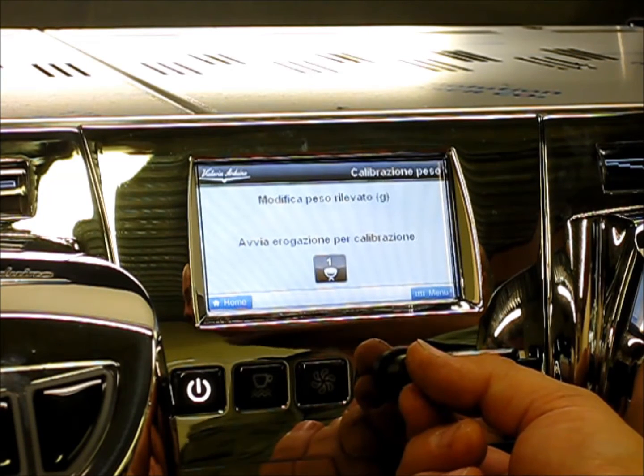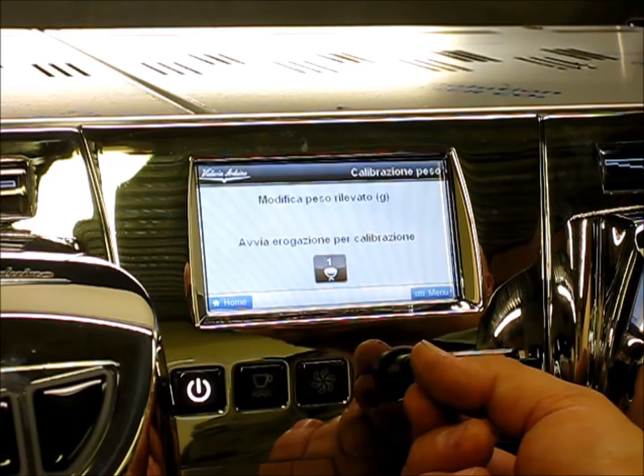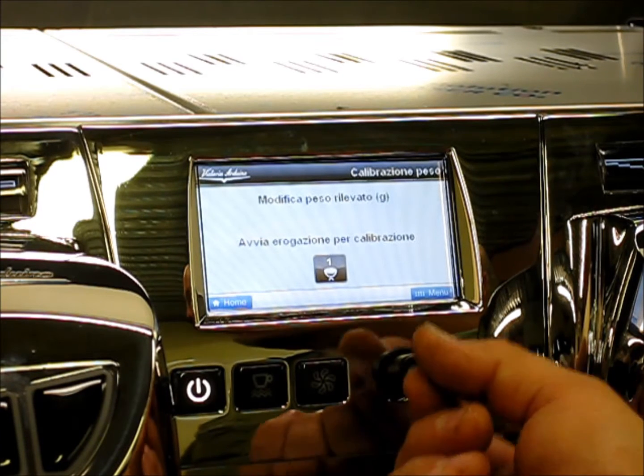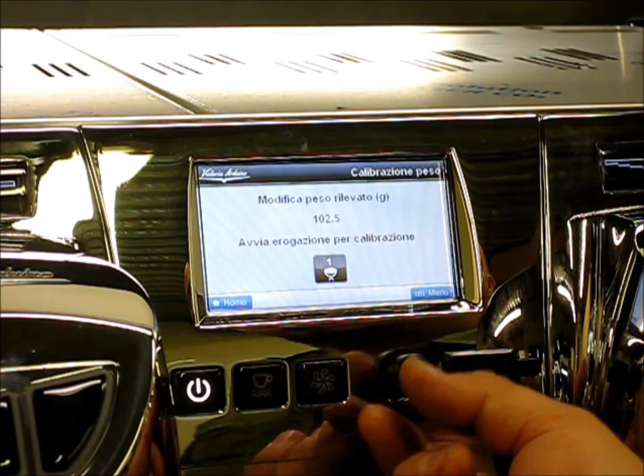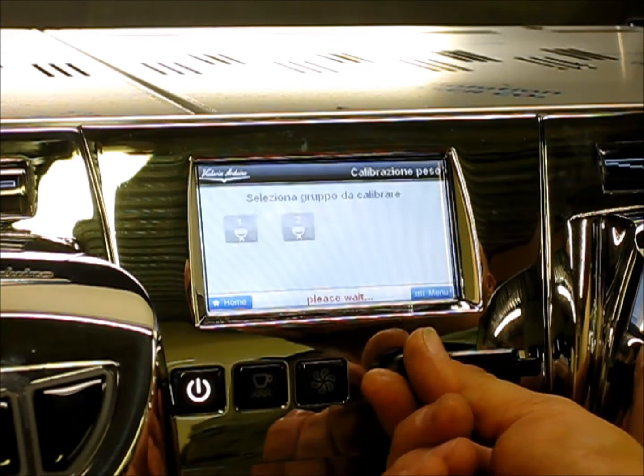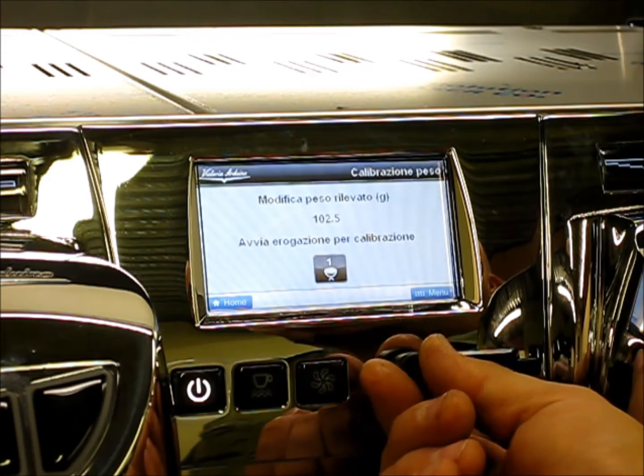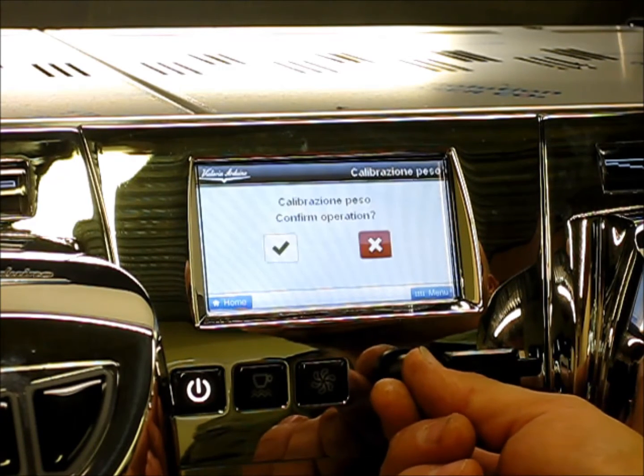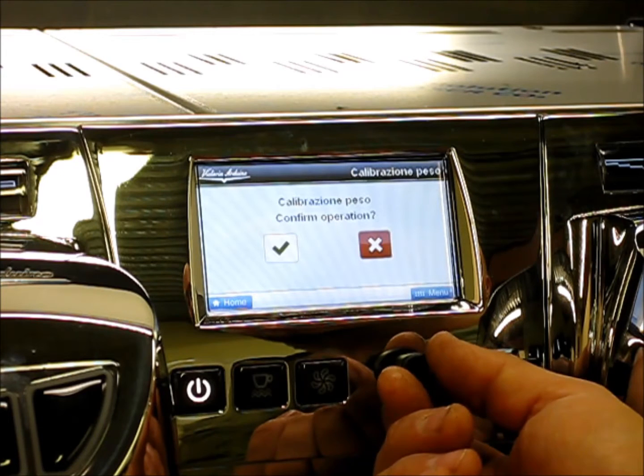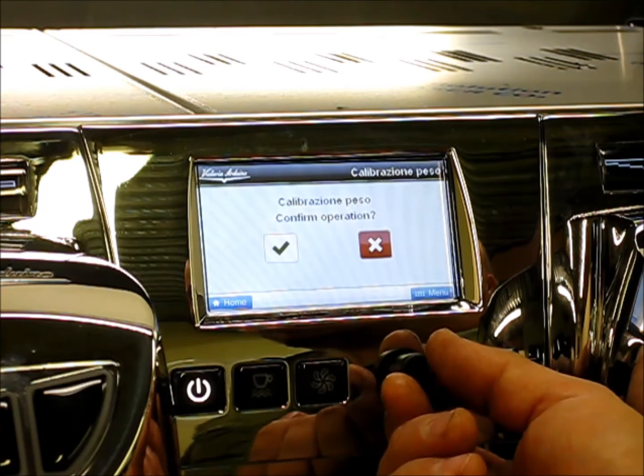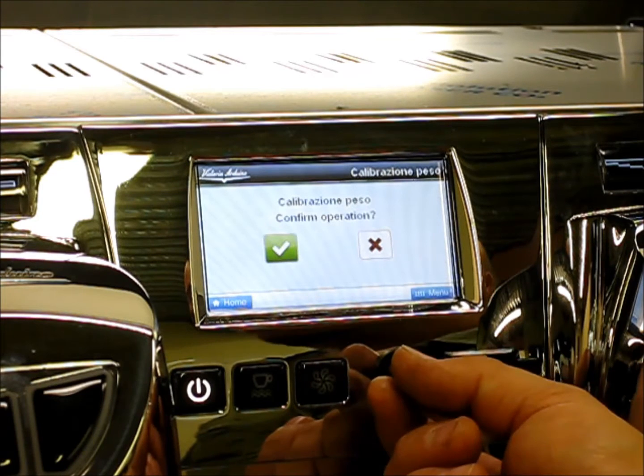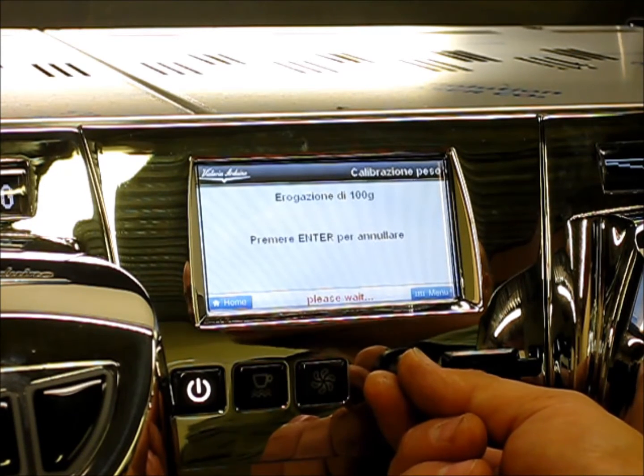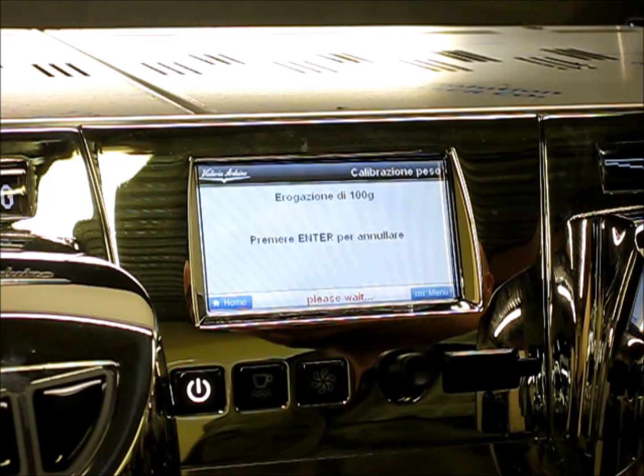Below that, we also have a calibration mode that will set the scale from 0 to a maximum of 100 grams. In this case, we're going to choose the option of calibration of the scale. Right now, it asks us to confirm the operation of calibrating the scale. If we highlight the green check mark, the machine will start the process of calibrating our scale. Again, this runs from 0 all the way to 100 grams.